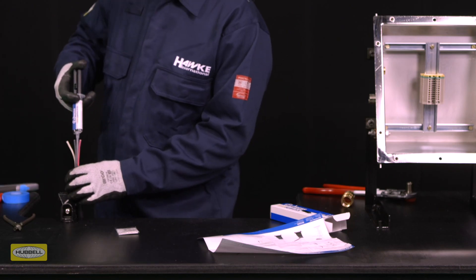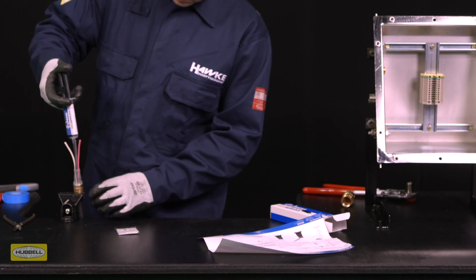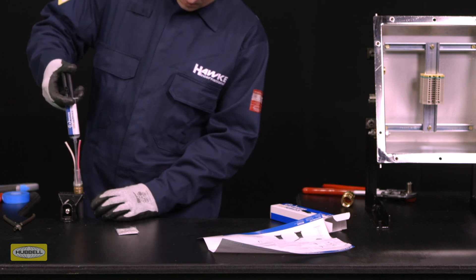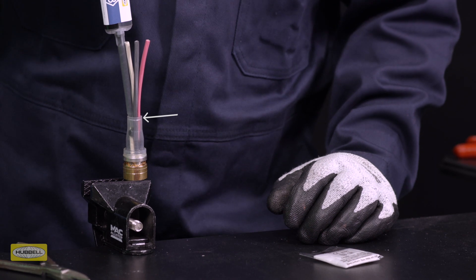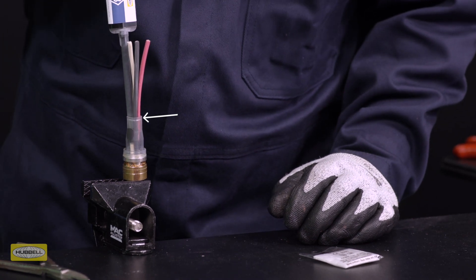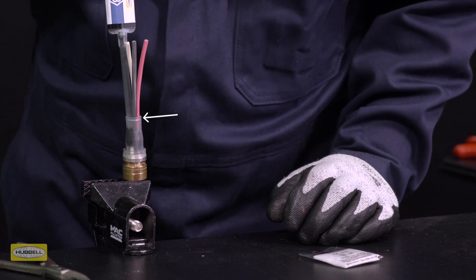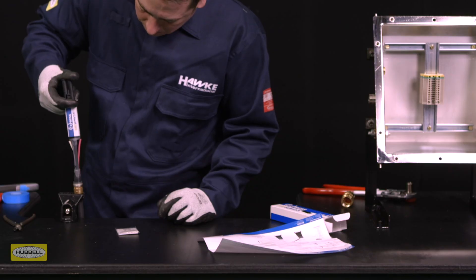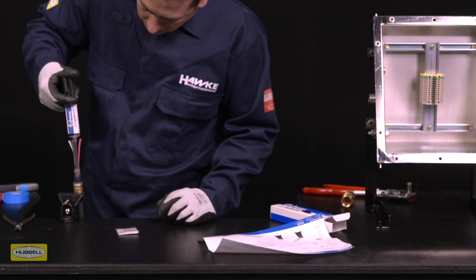Ensure the gland is held vertically. With the nozzle starting as far down the pot as possible, fill the resin to approximately 3 millimeters under flush. This is indicated on the silicone pot by the fill line shown on screen. Check that the resin is properly filled without any voids.